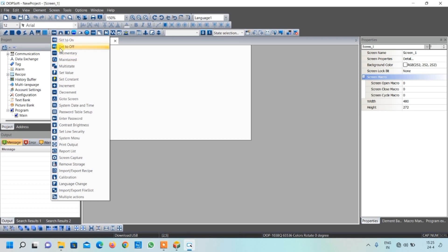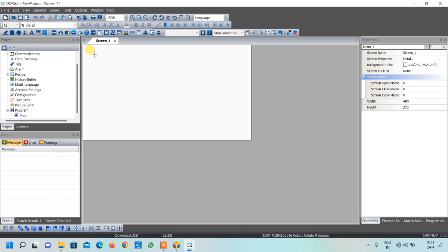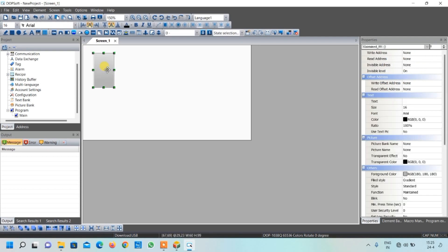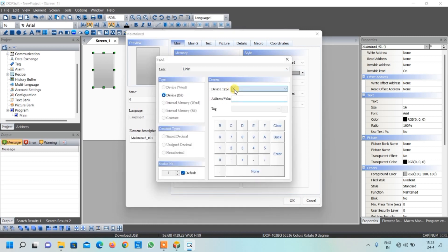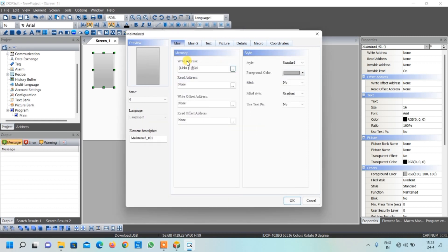To create the start/stop button, select 'Maintain' and draw a rectangular box. Double-click it and this dialog box will open. The first step is to write the address - the start/stop button is connected at X0 in the PLC, so select X and 0 and press Enter. This box now represents the X0 terminal of the PLC.